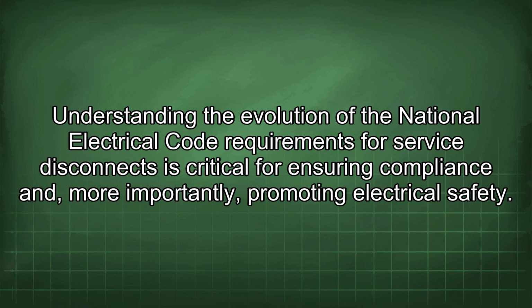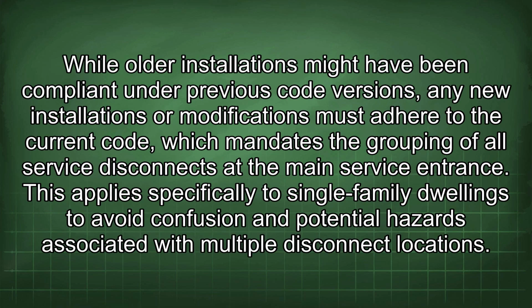Understanding the evolution of the National Electrical Code requirements for service disconnects is critical for ensuring compliance and, more importantly, promoting electrical safety. While older installations might have been compliant under previous code versions, any new installations or modifications must adhere to the current code, which mandates the grouping of all service disconnects at the main service entrance. This applies specifically to single-family dwellings to avoid confusion and potential hazards associated with multiple disconnect locations.